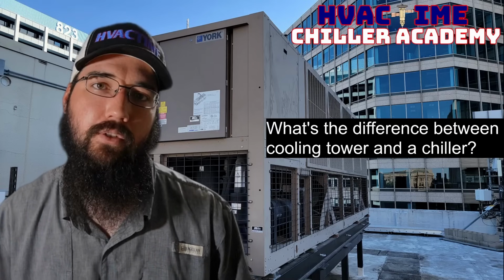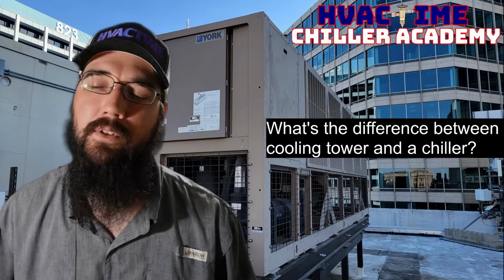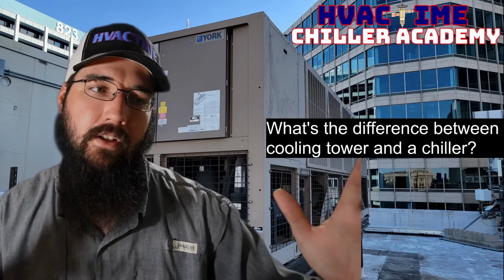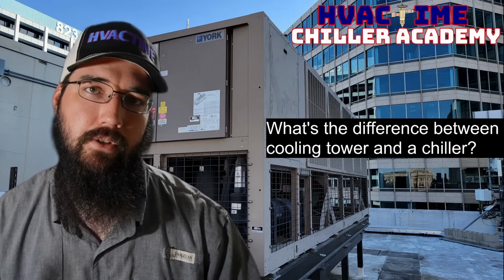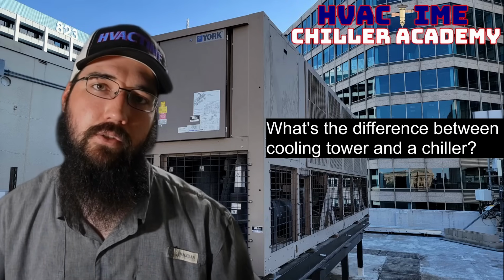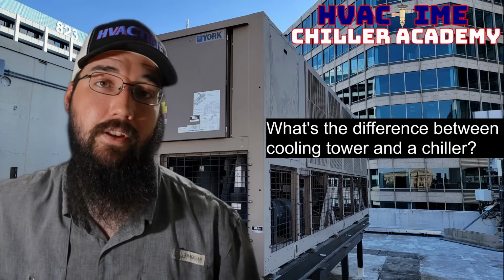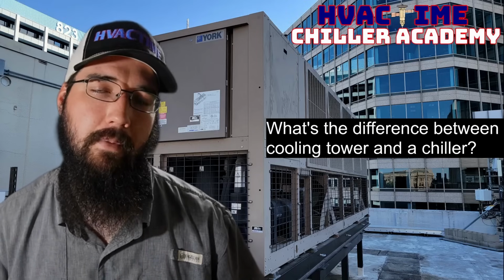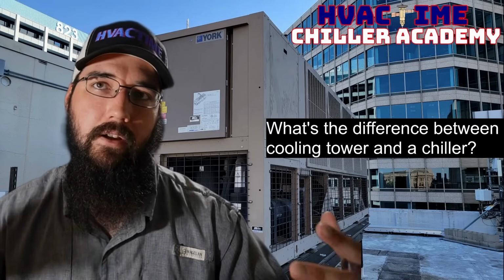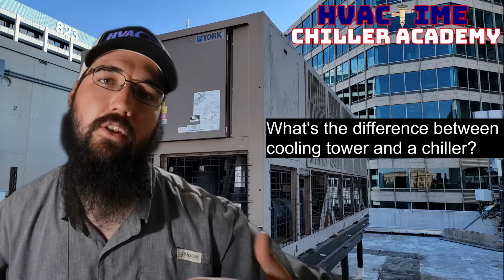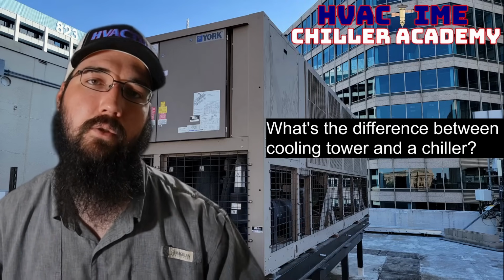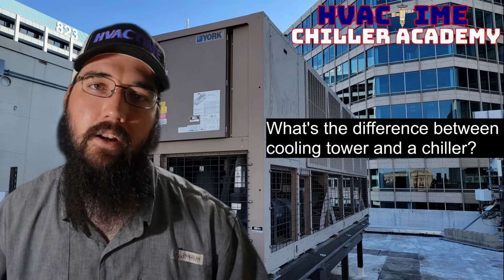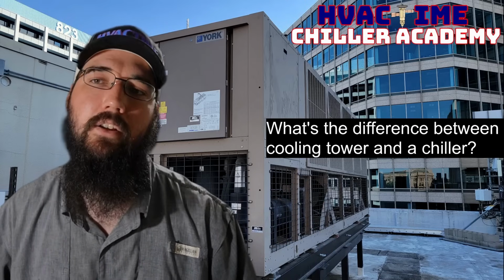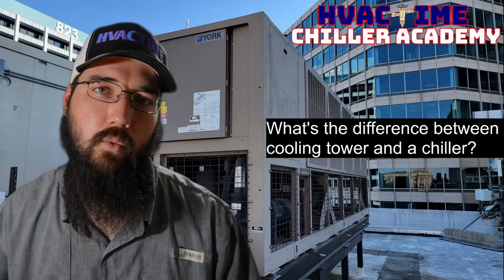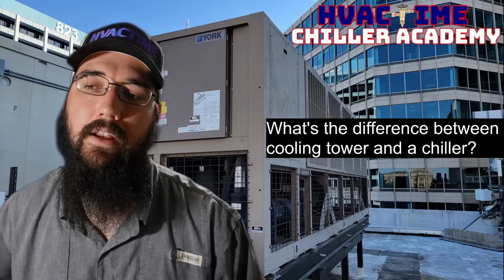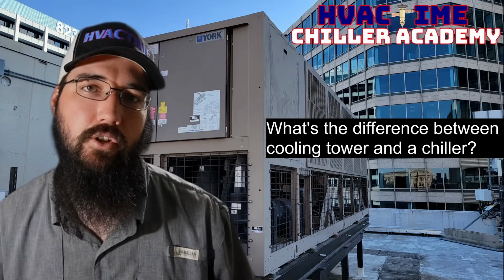Now, cooling towers can be used on a variety of applications. We could use it for water source heat pumps. We could use it for self-contained equipment, where basically it's an indoor air handler with all the refrigeration built in, and we have a water-cooled condenser, and that water-cooled condenser just pushes all the heat out to the cooling tower. The cooling tower throws the heat out and sends cooled water back to the condenser. But those aren't considered chillers because, like with a self-contained, you still have an air over evaporator coil. We're still moving air across a coil, it's an air handler with a blower. All that process is still happening. So it's just a regular air conditioning system with a water-cooled condenser. So cooling towers are still used in other applications outside of just chiller equipment.